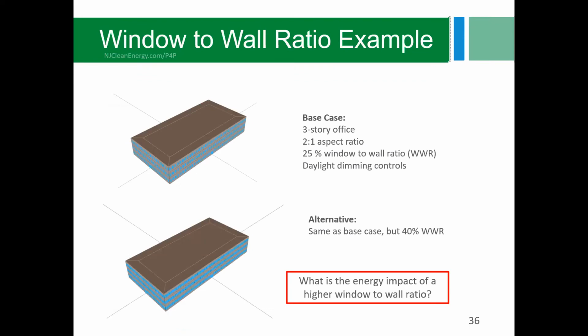Okay, here's an example for this one. We have our base case, which is a 3-story office, 2-to-1 aspect ratio, with a 25% window-to-wall ratio and daylight dimming controls. The alternative we want to look at is the same as the base case, but with a 40% window-to-wall ratio.